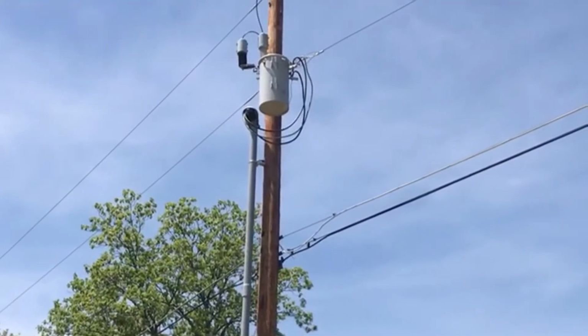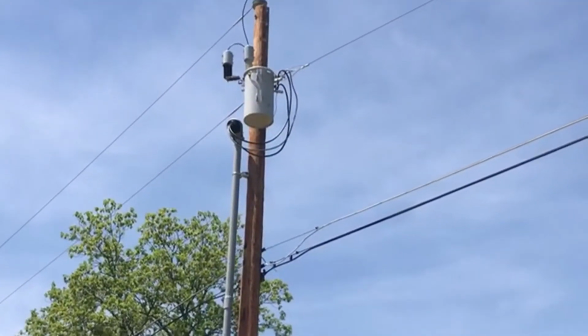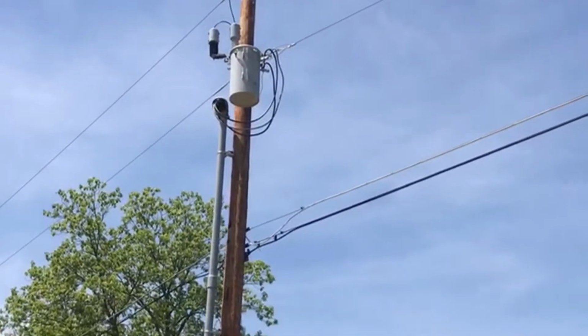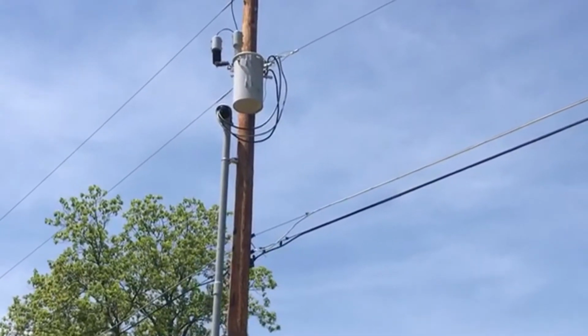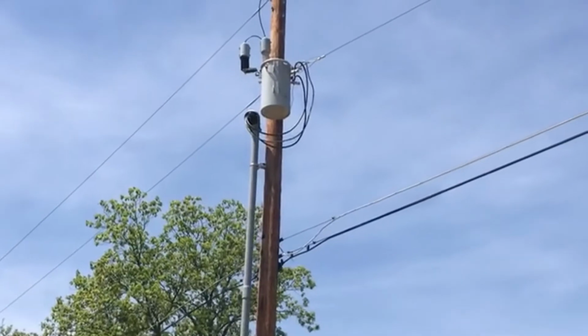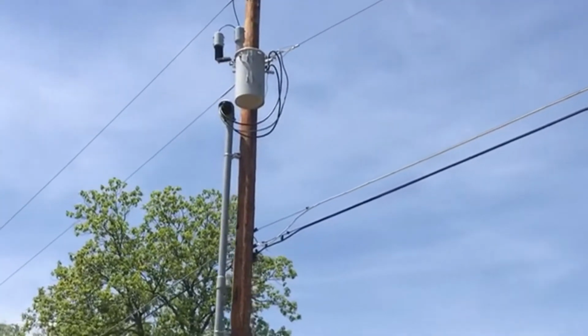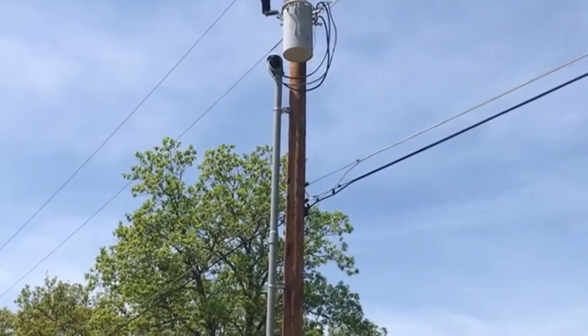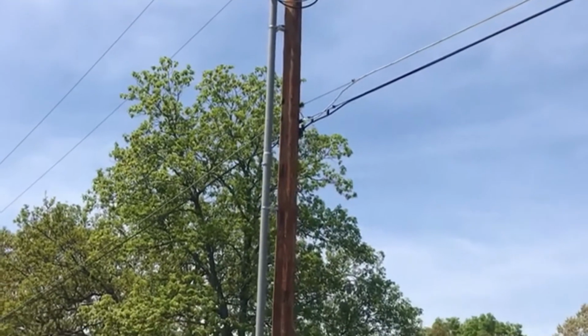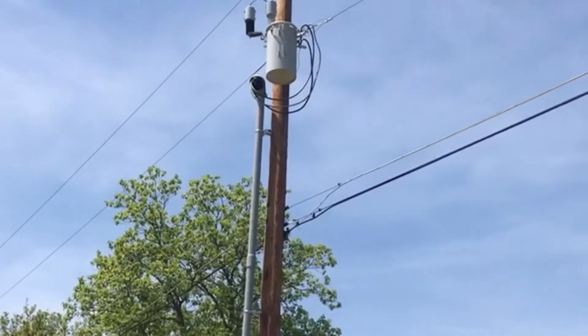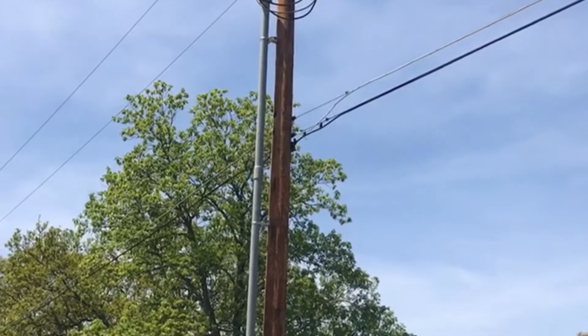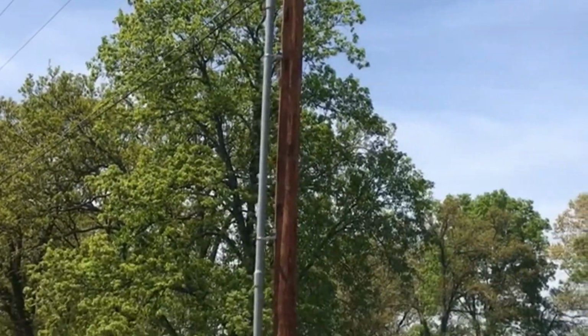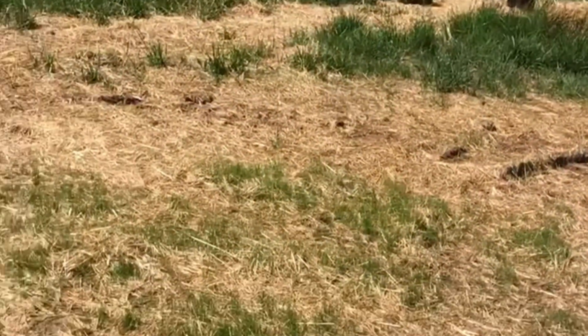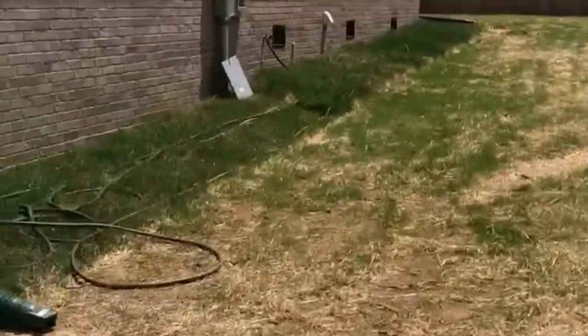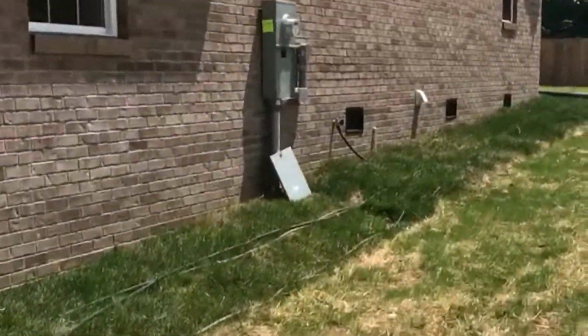From the primary to the transformer steps down the voltage to 120 to 240 volts. Instead of doing an overhead service, we chose to do an underground service. The 240/120 volt service goes down this conduit, buried 36 inches underground to meet codes, and goes to the meter attached to the side of the house.